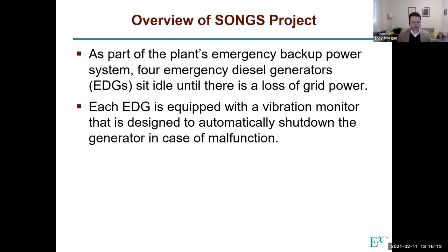Now these generators, as I'll discuss, are equipped with a special vibration monitor, a little device mounted to the top, which measures vertical movement. The point is, if the rotational movement is excessive—let's say there's a loss of a part of the rotational equipment that causes eccentric loading—it'll cause excessive vertical vibration, and that is a sign of malfunction. This vibration monitor will read that movement and then shut the power off to the generator so it doesn't blow itself up.